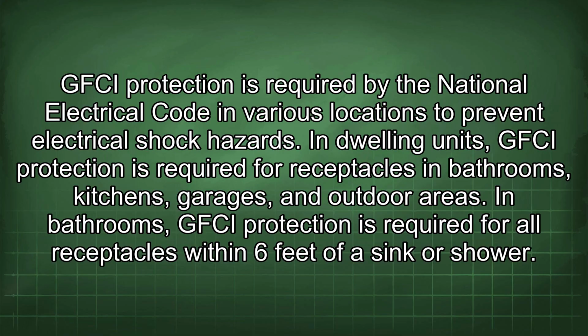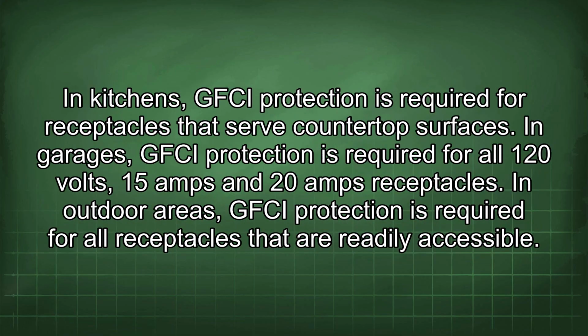In dwelling units, GFCI protection is required for receptacles in bathrooms, kitchens, garages, and outdoor areas. In bathrooms, GFCI protection is required for all receptacles within 6 feet of a sink or shower. In kitchens, GFCI protection is required for receptacles that serve countertop surfaces. In garages, GFCI protection is required for all 120 volts, 15 amps and 20 amps receptacles. In outdoor areas, GFCI protection is required for all receptacles that are readily accessible.